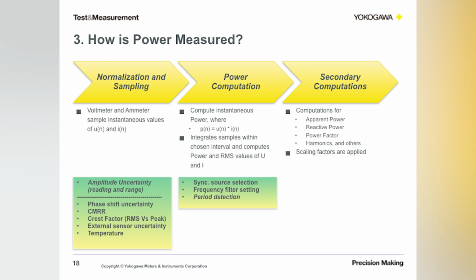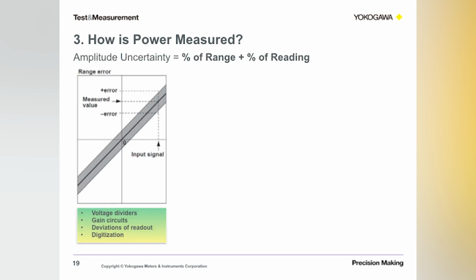So most of the uncertainties are contributed from the first two steps of this measurement process. Let's take a look at the amplitude uncertainty and how you state it. That comes from the first step. In general, it is expressed in terms of percentage of range and percentage of reading. The range error, as I've shown here, comes from the analog side of the input circuitry that normalizes your signals, which in turn is digitized by passing through the A to D converter.